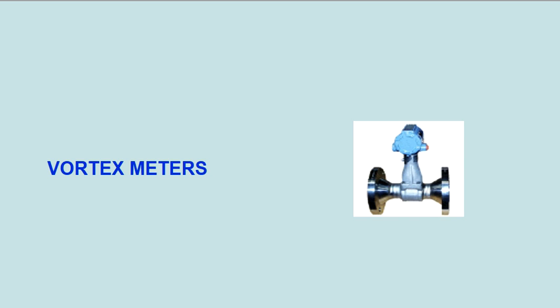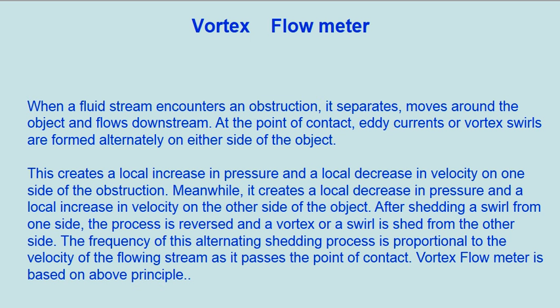At the point of contact, eddy currents or vortex swirls are formed alternately on either side of the object. This creates a local increase in pressure and a local decrease in velocity on one side of the obstruction. Meanwhile, it creates a local decrease in pressure and a local increase in velocity on the other side of the object.